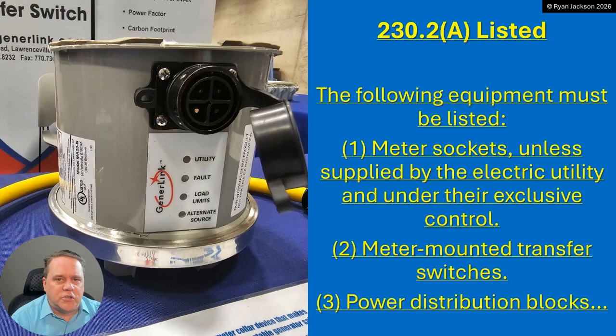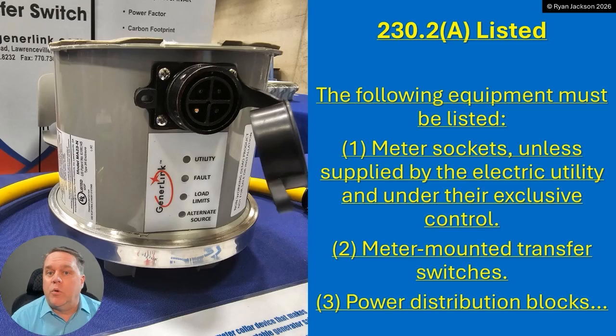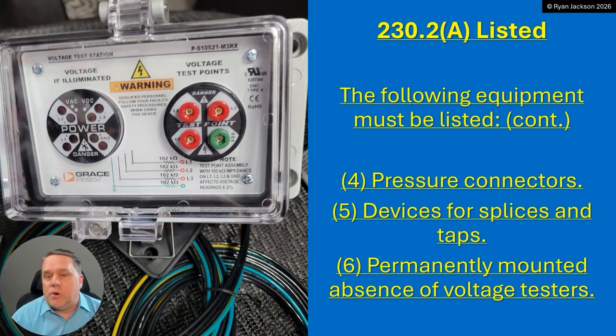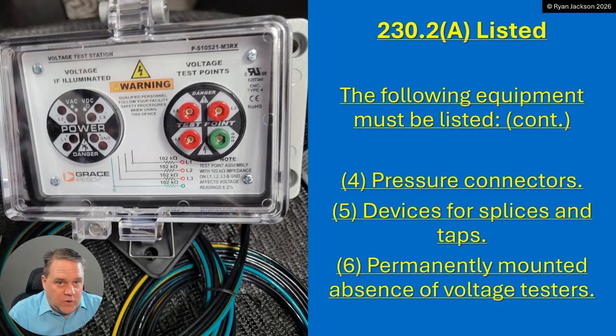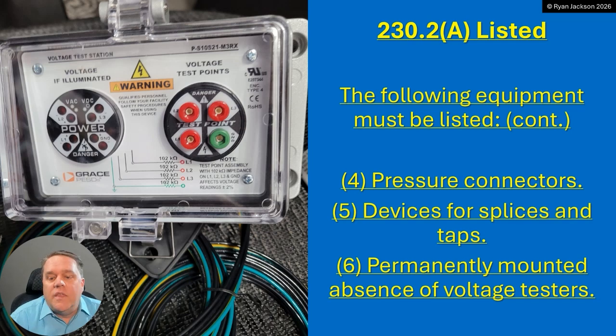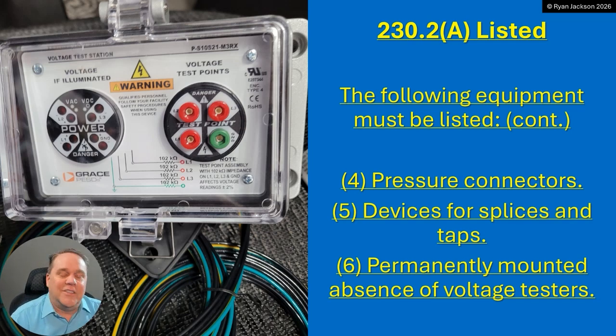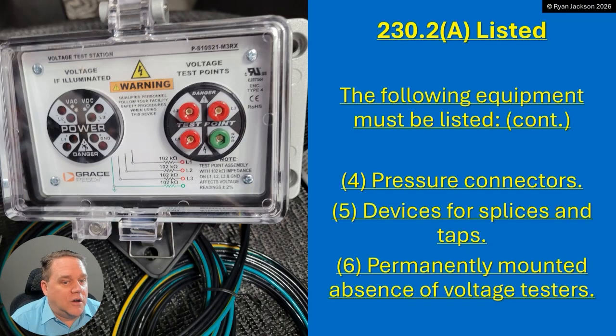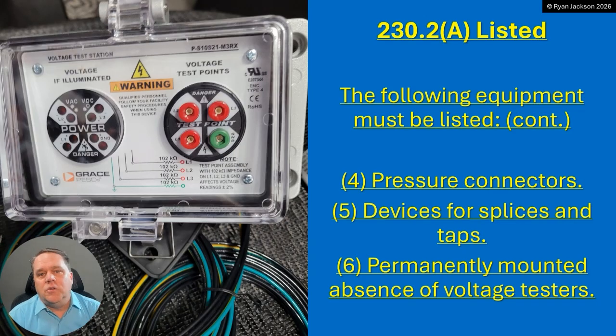Item three: power distribution blocks have to be listed products — that would be the item you'd maybe put in a wireway to make multiple splices. Pressure connectors have to be listed products — typically what you use for a lug has to be a listed product. Item five: devices for splices and taps, which are also usually pressure connectors — that would be power distribution blocks, a lug, twist-on wire connector, push-in wire connector — anything you're using to splice or tap service conductors has to be listed.